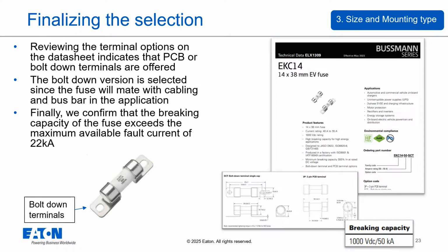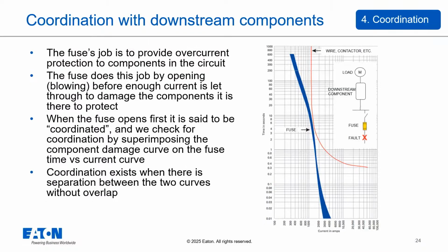A fuse's main role is providing overcurrent protection to everything connected after it in the circuit. Its job is to open or blow quickly enough during a fault so that not enough current passes through to damage components like wires, contactors, or other devices. When the fuse clears the fault before these downstream components are damaged, we say the fuse is coordinated.